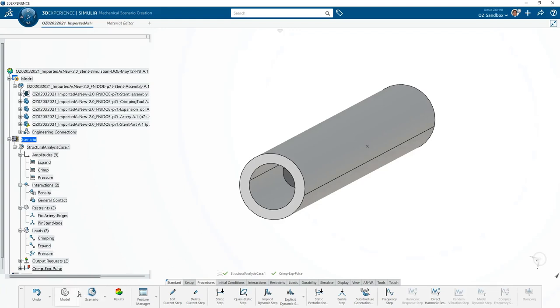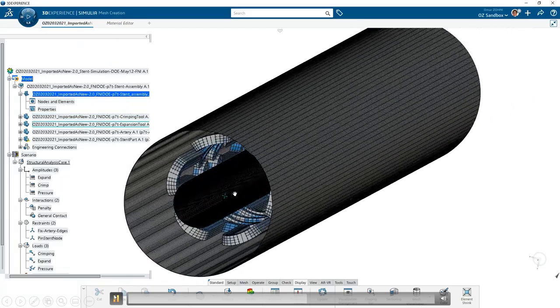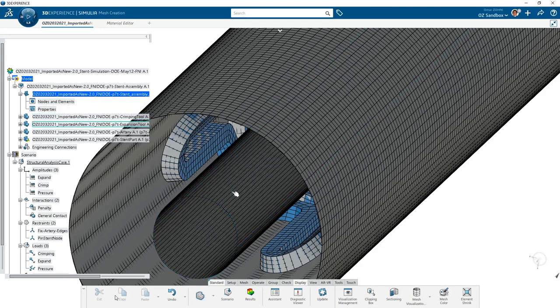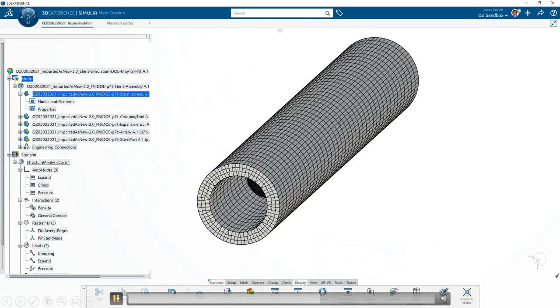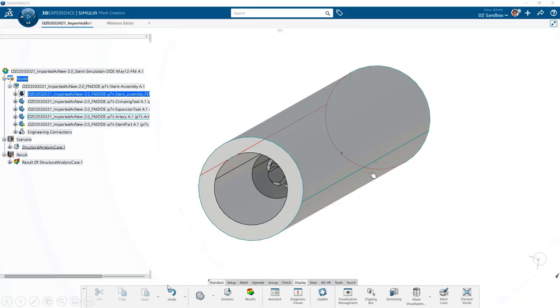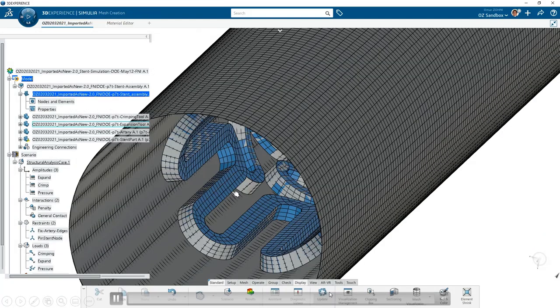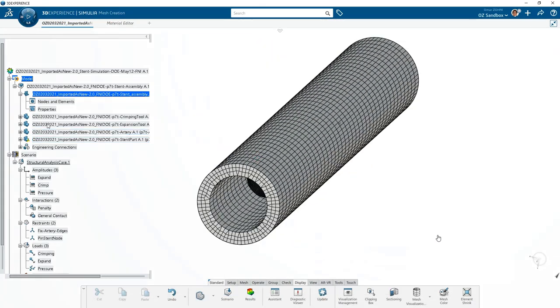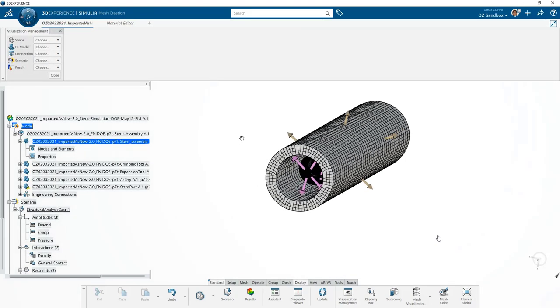As far as restraints go, there are two: fixing the artery edge and pinning a node on the stent to stabilize it. The loads include crimping, expansion, and pressurization applied through both displacements and input pressure. The automated sweep mesher applies hexahedral elements to really complicated geometry. For a large deformation analysis like this, it is recommended to utilize a full hexahedral mesh or a combination of hexahedral and quad mesh to execute the analysis with accuracy and speed.